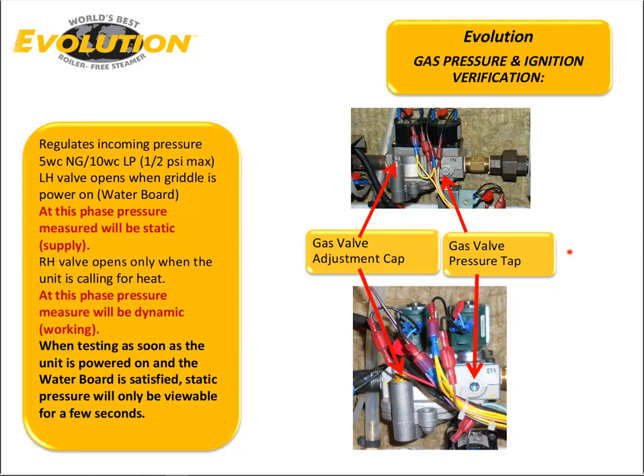Once we close the door to the steamer, the second valve, which is the valve on the right, will open. At this point, the pressure should drop, and that is your dynamic pressure. We prefer to see this around 5 inches water column. There is about 1/2 a water column leeway on either side to get the better signal from the flame sense. We'll go into that later. But the standard we say is 5 inches water column. If that second valve opens and you see a higher or a lower pressure, it can be adjusted here or here. You'll have to remove the adjustment cap first. That'll give you access to the plastic regulator screw, which you can back out or push down to increase or decrease pressure.